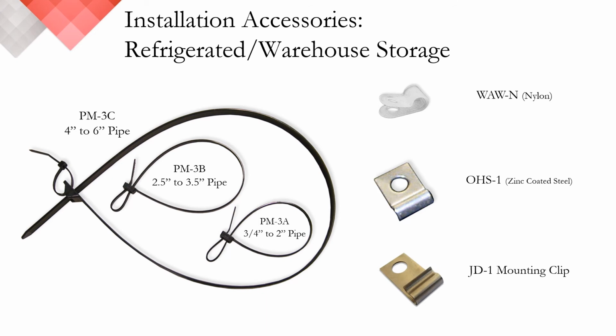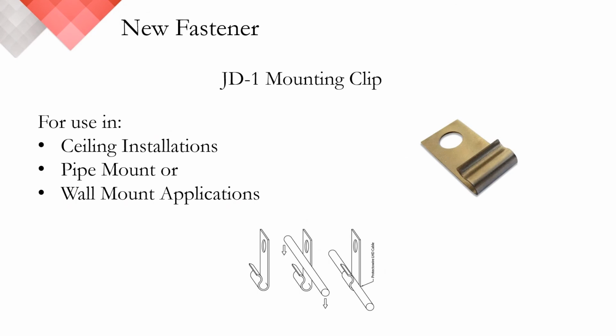For in-rack, we have a variety of clips available to accommodate the installation, including our WAW nylon clips, our OHS clip, and our newly introduced JD1 clip. The JD1 was recently introduced to provide installers an easier method of supporting and installing linear heat detection. Most, if not all, of the supports offered are a closed-loop format. These have been effective accessories for a great many years, but are sometimes problematic when making repairs. To do so would require the removal of clips and then reinstalling. The JD1 design resembles a J-slot, with an open top and slightly narrowed opening. The open top allows for quick installation and removal without the need to remove or replace the clip, saving you both time and money.